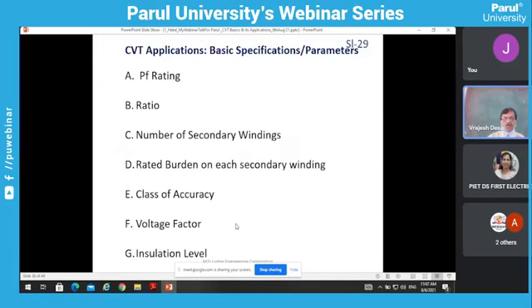Now we are going toward the basic specifications. We have talked about all the applications. Now we have to see how we want to specify the CVT. Suppose somebody wants a CVT, then what are the basic specifications? Those specifications are: first, the PF rating; second, the ratio; third, the number of secondary windings; fourth, the rated burden on each secondary winding; class of accuracy; voltage factor; and finally the insulation level.